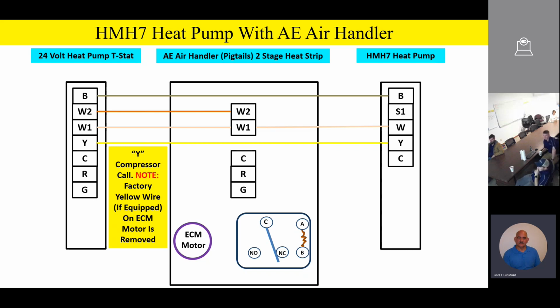But the way the unit works outside, now remember, team, on the indoor coil, you're going to have just a conventional expansion valve. It's nothing fancy. It's just a regular heat pump. You have an expansion valve on the indoor coil. However, the outdoor unit, it's equipped outside with an EEV, so it can monitor and it can also control the liquid refrigerant flow outside through its own EEV.